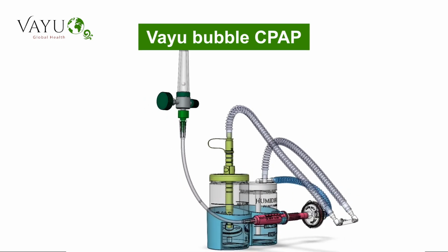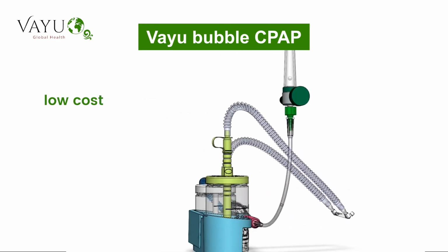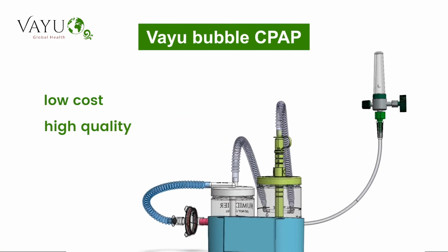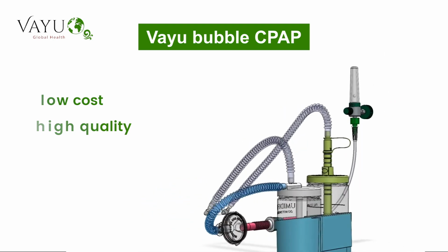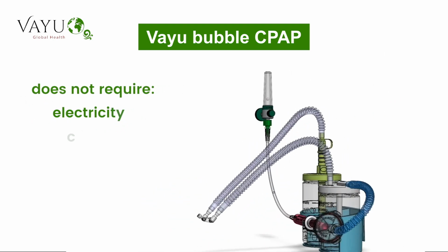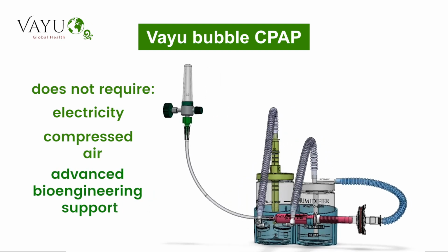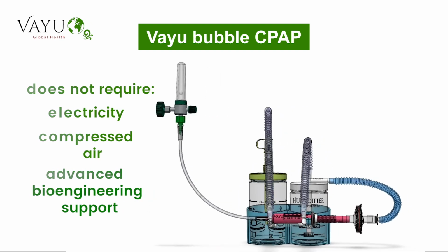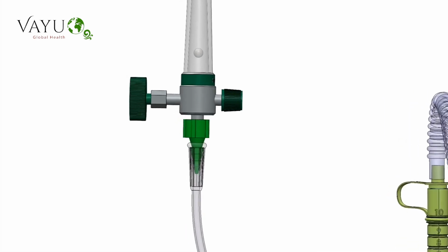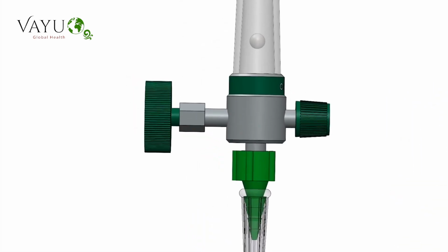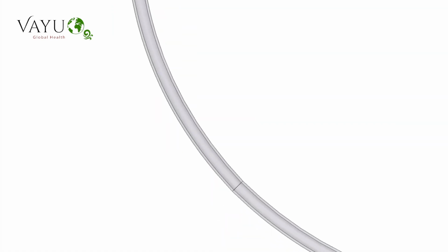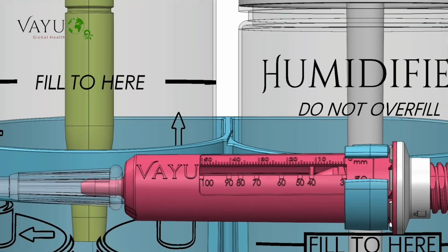The Vayu bCPAP system is the first low-cost, high-quality newborn and infant CPAP system that does not require electricity, compressed air, or advanced bioengineering support. The Vayu bCPAP system uses an external oxygen source, such as a wall source, oxygen cylinder, or high-pressure oxygen concentrator. From the source, oxygen tubing connects to the Vayu blender.